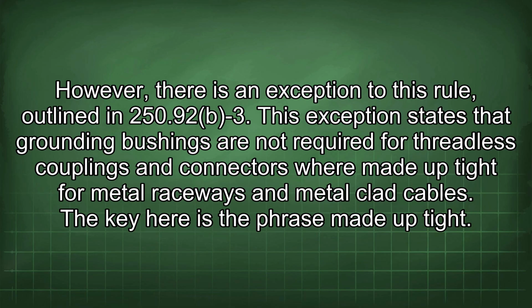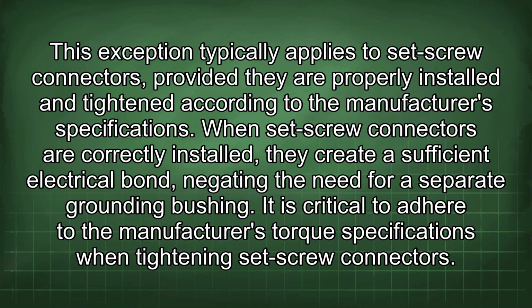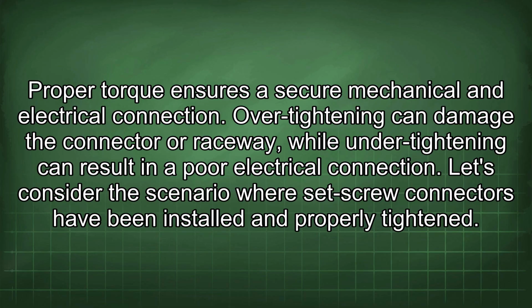However, there is an exception to this rule outlined in 250.92(b)-3. This exception states that grounding bushings are not required for threadless couplings and connectors where made up tight for metal raceways and metal-clad cables. The key here is the phrase "made up tight." This exception typically applies to set screw connectors, provided they are properly installed and tightened according to the manufacturer's specifications. When set screw connectors are correctly installed, they create a sufficient electrical bond, negating the need for a separate grounding bushing. It is critical to adhere to the manufacturer's torque specifications when tightening set screw connectors. Proper torque ensures a secure mechanical and electrical connection. Over-tightening can damage the connector or raceway, while under-tightening can result in a poor electrical connection.